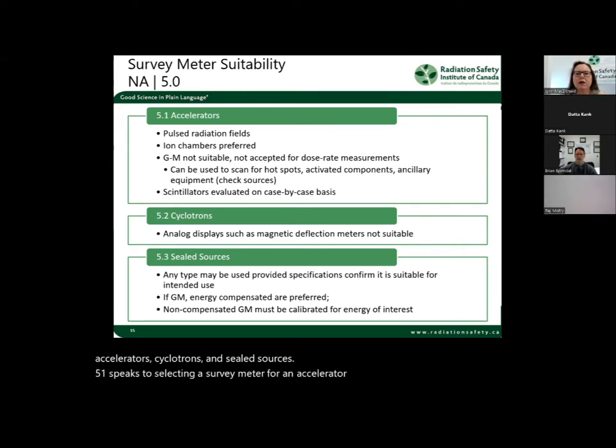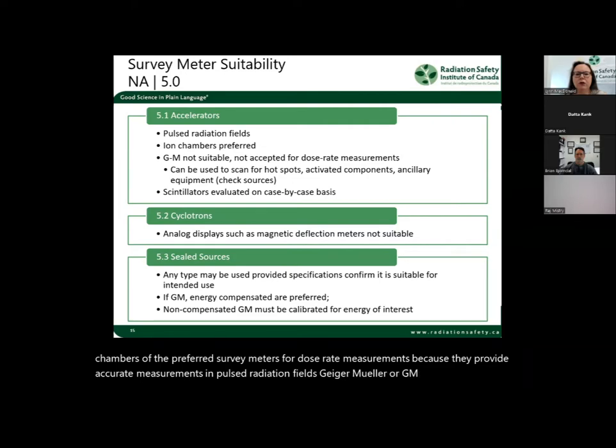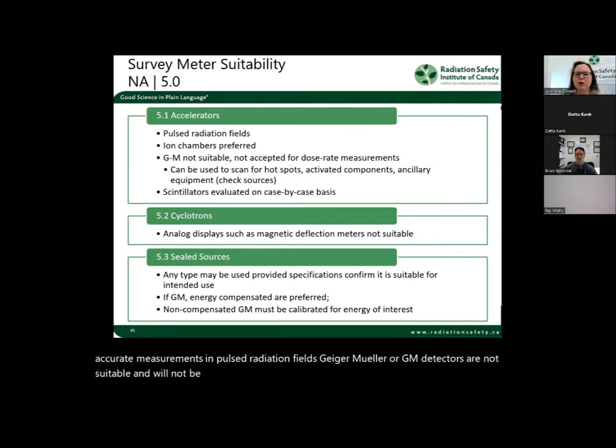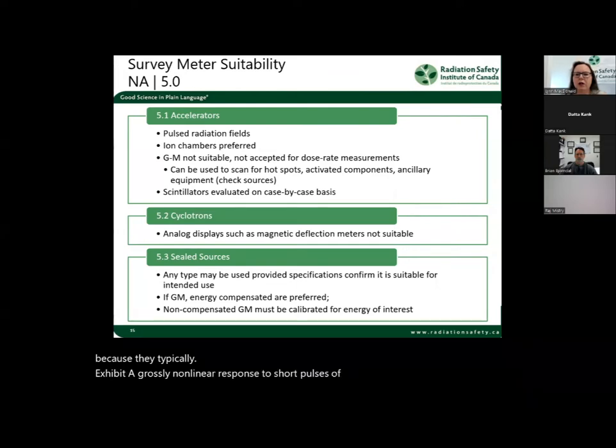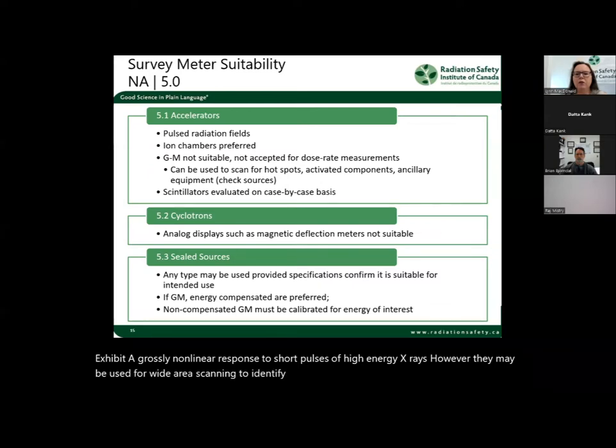Some accelerators, such as medical accelerators, produce very short pulses of high energy X-rays. For such accelerators, ion chambers are the preferred survey meters for dose rate measurements because they provide accurate measurements in pulsed radiation fields. Geiger-Müller or GM detectors are not suitable and will not be accepted for dose rate measurements in those accelerator facilities because they typically exhibit a grossly nonlinear response to short pulses of high energy X-rays. However, they may be used for wide area scanning to identify hotspots during room surveys, provided dose rate measurements are subsequently taken with an ion chamber or other suitable instrument.